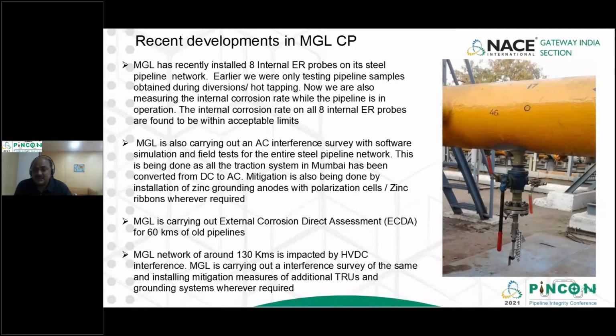It used to be a big challenge for us to monitor the pipelines, and to ensure that there isn't excessive voltage on the pipeline which can result in cathodic disbondment. But during the course of the last 6-7 years, the suburban trains have transited from DC to AC. So we are now done with DC interference. Now we have AC interference, but that is not a very big challenge compared to the DC interference which we used to have previously. Mitigation is done by installing zinc grounding anodes, with a polarization cell and zinc ribbons wherever required.